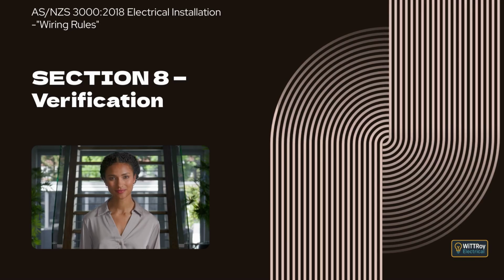Clause 8.1.2 General Requirements. This clause explains that before an electrical installation, or any part of it, is put into service after construction, alteration, or repair, it must be verified as far as is practical. Verification is done to make sure the installation is safe to energize and will operate in line with the requirements of this standard. It also explains that once the work is finished and before the installation is put into service, the installation must be inspected in line with Clause 8.1.3 and Clause 8.2 as far as is practical, and it must be tested in line with Clause 8.3.